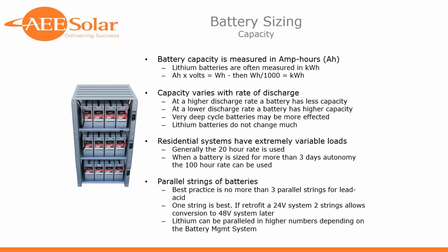You will, of course, need some paralleling equipment for any of those scenarios, right, Brad? I think a little more straightforward on the 2 to 3 strings of 24 or 48-volt strings. But on the lithium front, when we hear from manufacturers that say the BMS can tolerate virtually unlimited paralleling, we've still got the consideration of how do you parallel that power and get it back to the inverter or the charge controller. It's sort of like a larger version of a solar array. You've got a whole bunch of parallel circuits, and so you're going to have combiners, and often requiring a fuse or a circuit breaker on each parallel block. Mm-hmm.